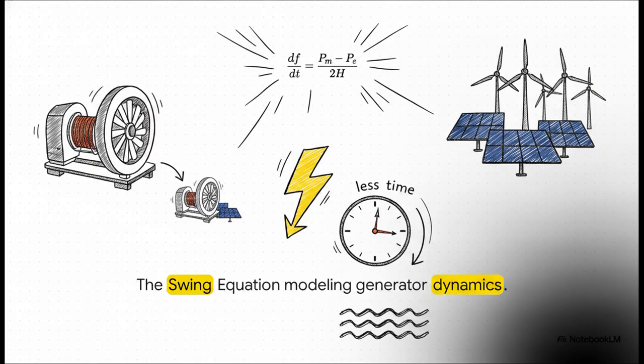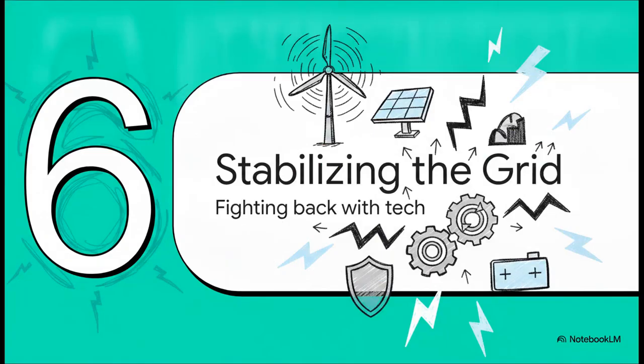We can actually see the math behind this crisis in something called the swing equation. That df/dt you see on the left is the rate of change of frequency, or RoCoF. The H in the denominator, that is the system's inertia. It's simple division. As H gets smaller, meaning we add more static renewables and retire more spinning turbines, that rate of change speeds up dramatically. So if there's a disturbance, the frequency drops incredibly fast. Grid operators and control systems suddenly have a lot less time to react before a total system blackout cascades across the network. Finally, Section 6, stabilizing the modern grid, how we're fighting back with cutting-edge tech.